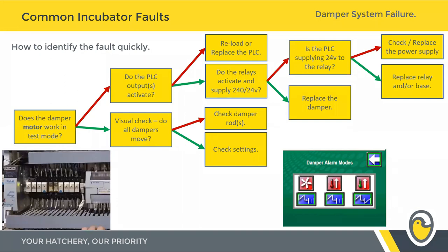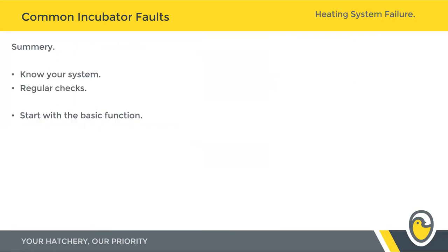If the relays are supplying 240 or 24 volts out to the damper, get that old damper physically removed and put a fresh one in its place, then verify with that control voltage that it moves. You've got to know your system — what damper you physically have on each of your machines. In a hatchery that's been expanded over the years, you may have mains-voltage dampers on older equipment and 24-volt dampers on newer equipment. Knowing that helps you identify exactly what that incubator needs in order for that damper to actuate.